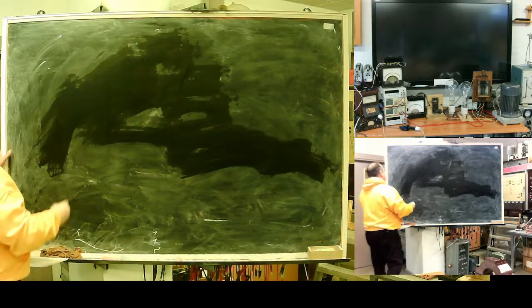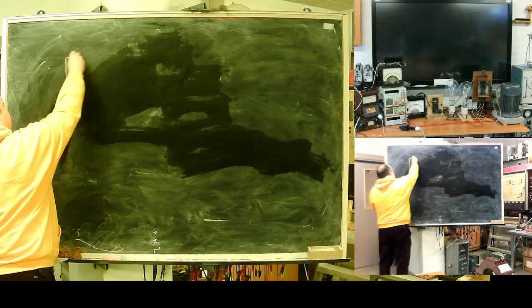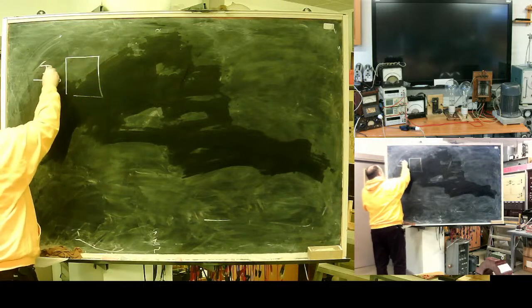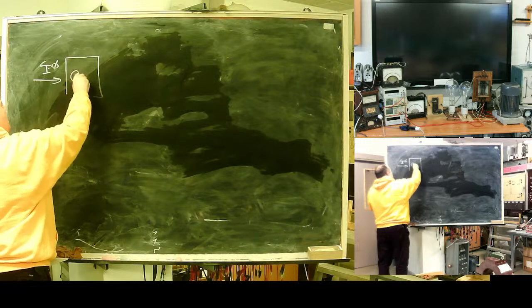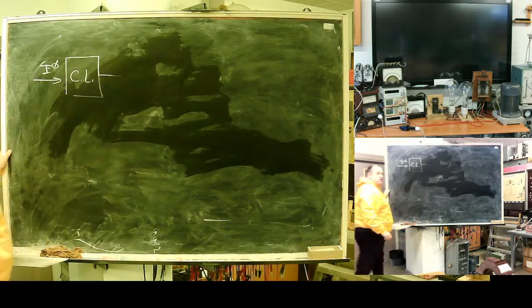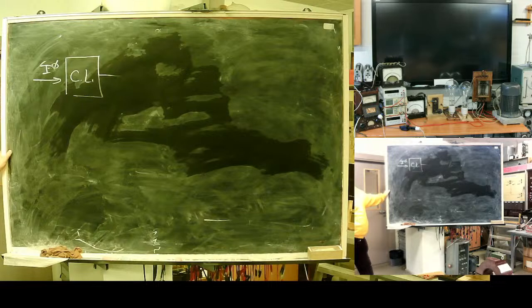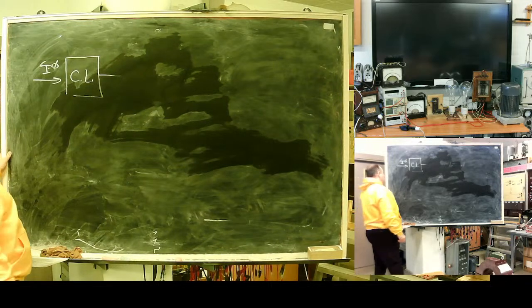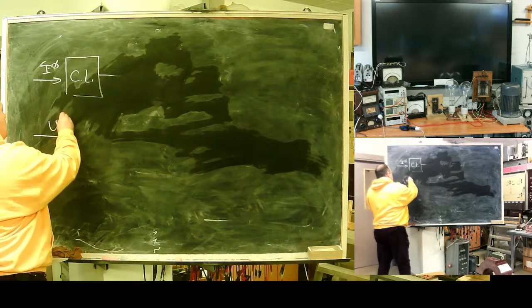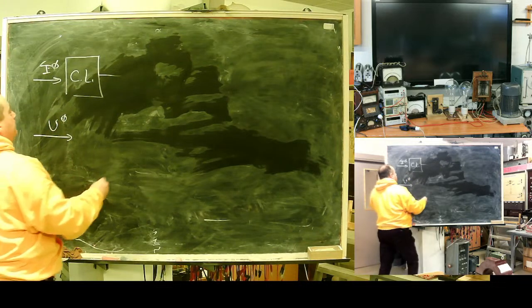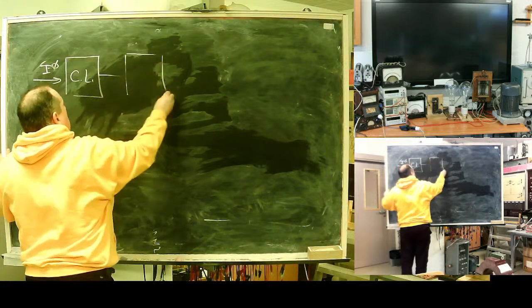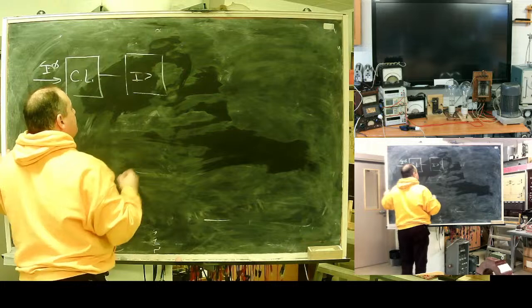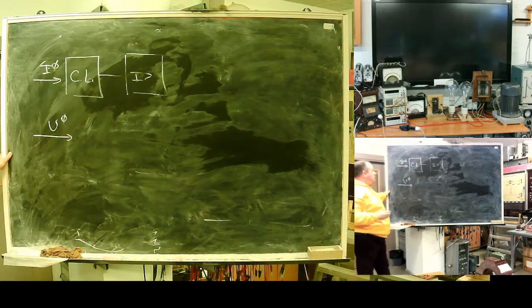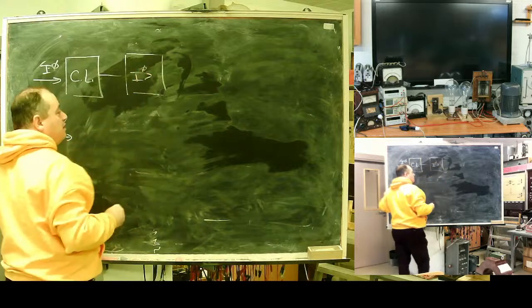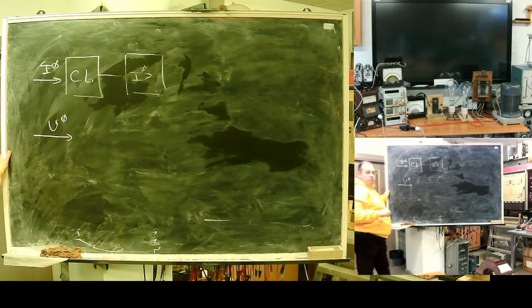So schematic, first one schematic of such protection. Zero sequence current, current limiter. Special circuit prevents damage in case of double line fault. Zero sequence voltage. One or more stage, zero sequence current generator. Can have multiple stages.